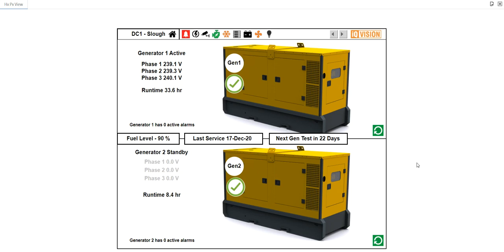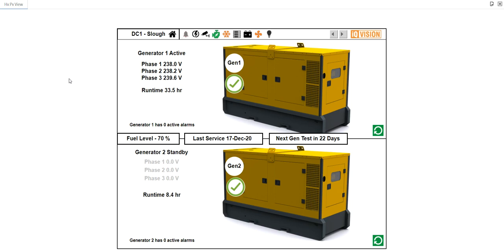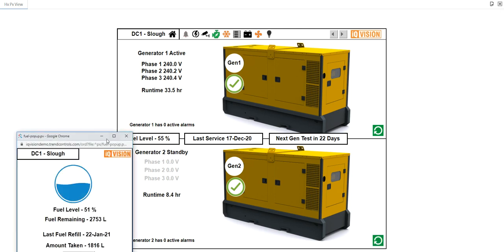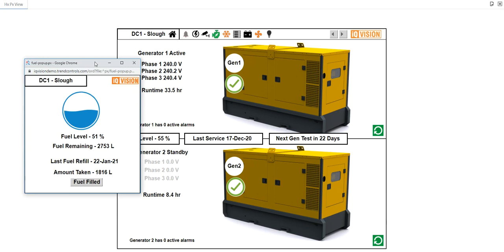IQ Vision is typically used to supervise trend systems for the most part. However, it is multi-protocol. It speaks many languages. For our example here, we are talking Modbus IP out to our generators. In some of the other examples, it could be SNMP to talk to equipment already in the racks. It could be MBUS to talk to meters. It could be BACnet to talk to chiller packs and so on. It very much is a capable and multi-protocol solution. You can see I've fixed my generator issue, which didn't take an awful lot of work, I'll admit.